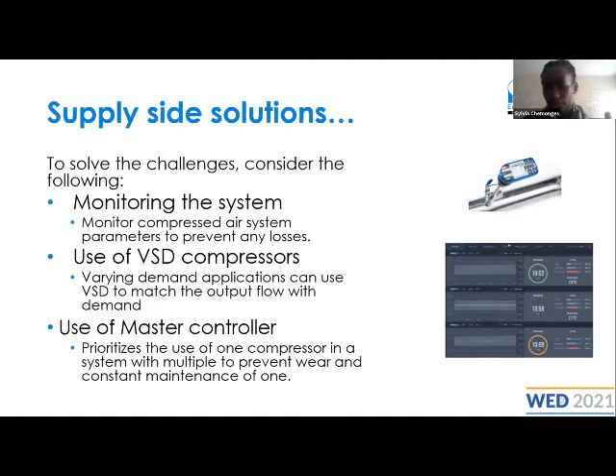Carry out monitoring of your compressed air systems. From the monitoring, we can look at how much energy you're consuming to supply compressed air to your machines. In case of any spikes or changes in the demand in your system, you can figure out how we are going to fix this to reduce the energy consumption. Maybe we need to change the machine, maybe we need to improve the piping, maybe we need to fix leaks. So monitoring is a very important part of minimizing losses within your compressed air system.